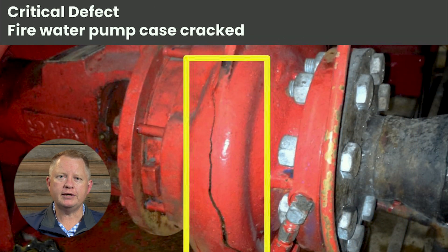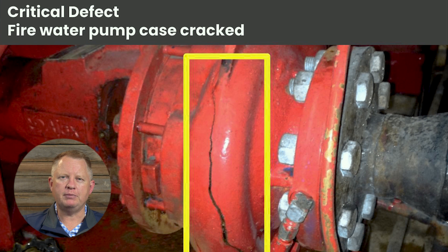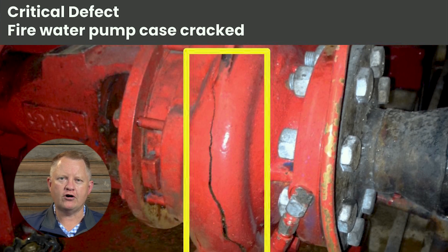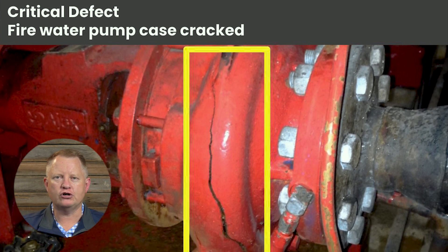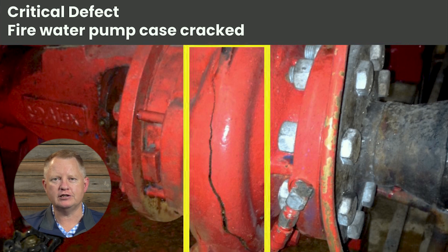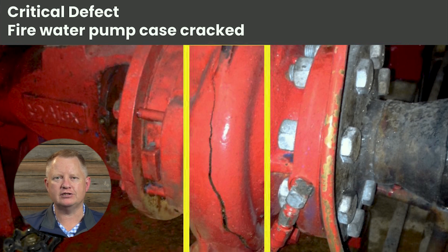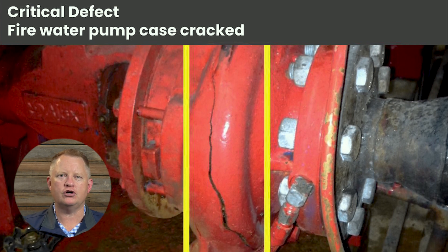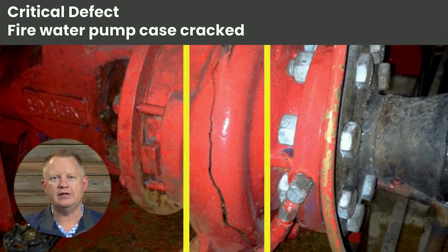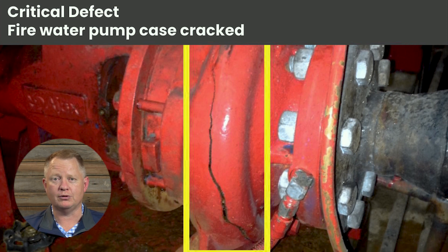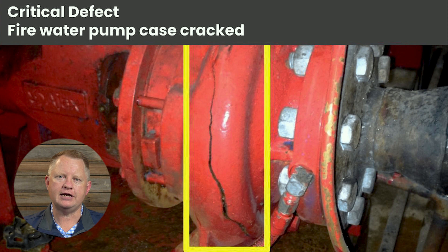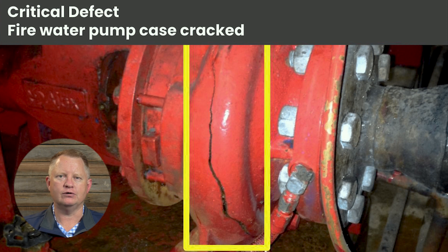This one is a bit unique. It's the housing of a fire pump that's been cracked. I would definitely call this a critical defect because it adversely affects the function of the entire system — the water supply. So that is definitely a critical defect.